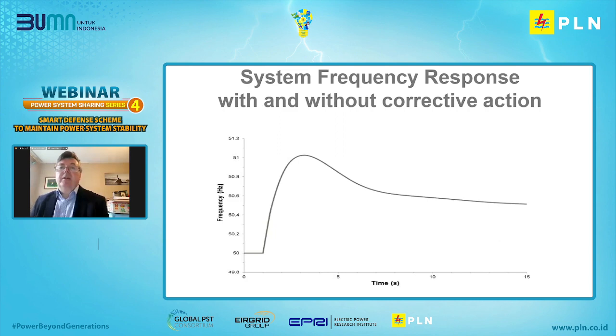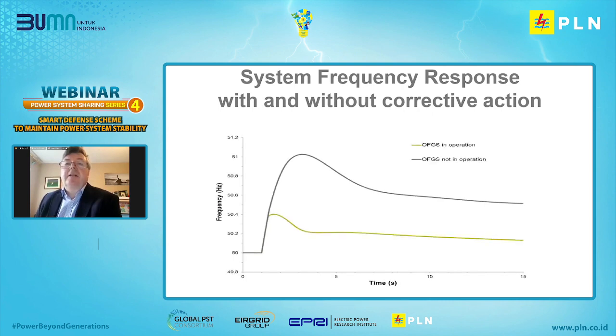So here's what will happen in our system if we lose a large export and we don't take corrective action. We'll go from 50 up to 51 hertz rapidly, in a matter of maybe 1 or 2 seconds. Advance to the next slide. The yellow trace there shows what happens when we have what we call our over frequency generation shedding in operation. It's arresting the rise at about 50.4 hertz, and then bringing it back down to normal over maybe a 15 or 20 second time period. Okay, next slide, please.